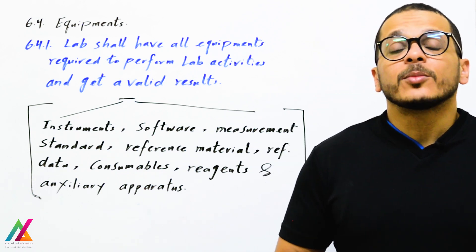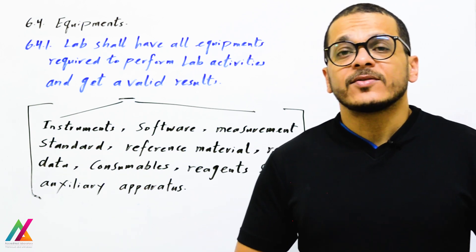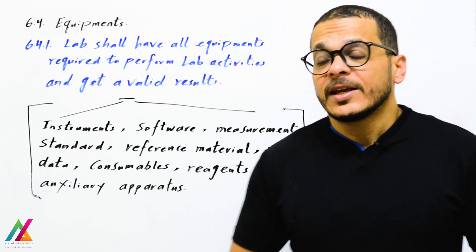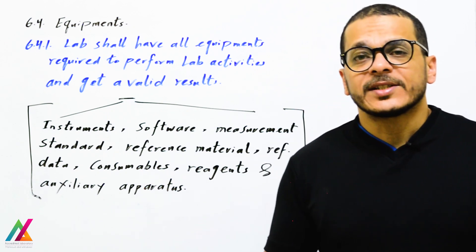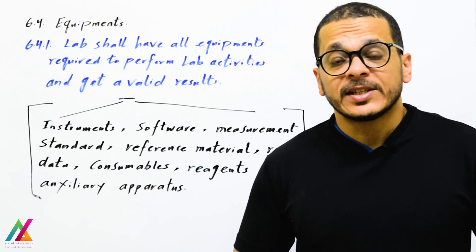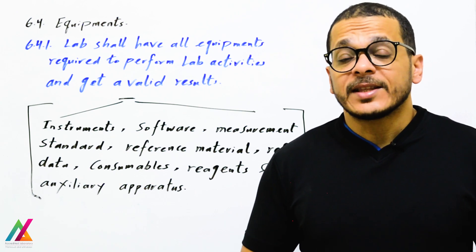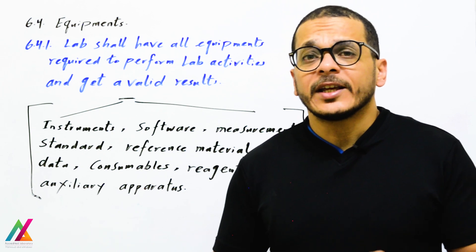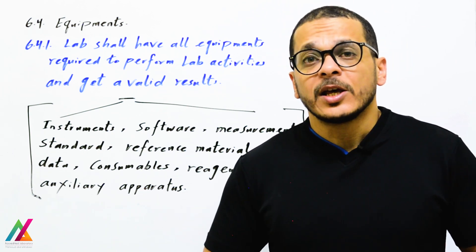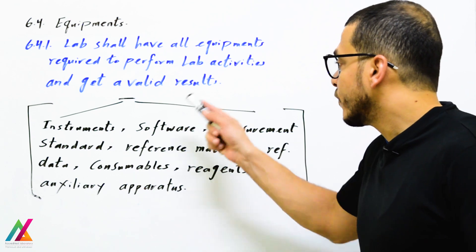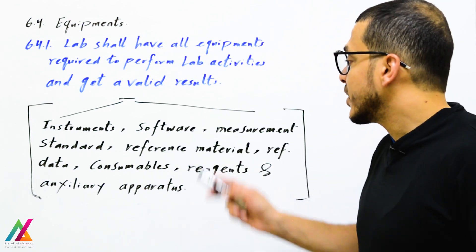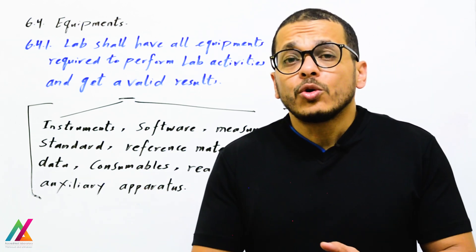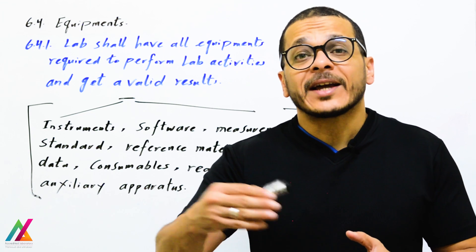Welcome back. This is a very important lecture on ISO IEC 17025 2017 edition, covering resources requirements and equipment. The lab shall have all equipment required to perform lab activities and get valid results. In the new 2017 edition, equipment is defined differently than in the 2005 edition — it doesn't only include instruments and auxiliary apparatus, but also software, measurement standards, reference materials, reference data, reagents, and consumables.